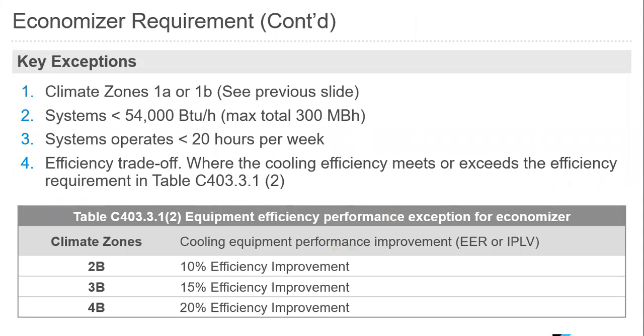When it comes to the economizer requirement, the key exceptions are for climate zones 1A and 1B, looking at the previous slides, systems less than 54,000 BTUs, and systems that operate less than 20 hours per week. And then there's also, number 4, an efficiency trade-off, which is what table C403.3.1 talks about. In climate zone 2B, we're looking for efficiency performance that's greater than 10%. In 3B, we're looking for efficiency performance that's equal to or greater than 15%. And in 4B, we need efficiency that's greater than 20%.